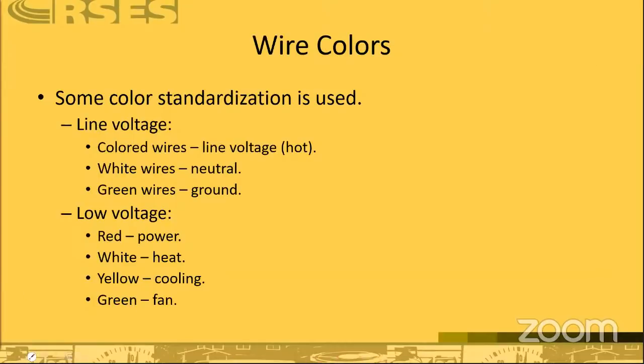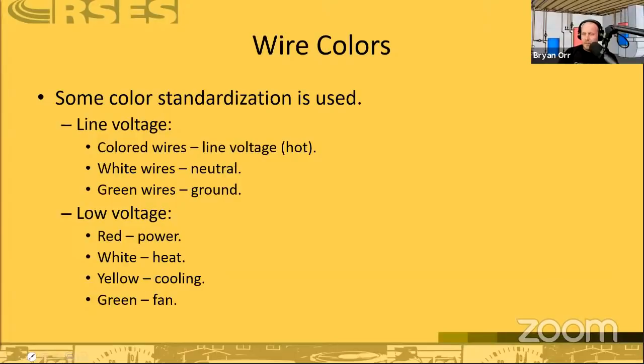Blue is common, and blue being common is one of the least set in stone, because you'll see black being used as common in some cases too. None of this really matters, you can use any color for any purpose, but as a standard we want to use the standardized colors. As another aside, if you're ever splicing wires in an 8-conductor thermostat cable, splice all 8 wires regardless of if you're only using 4 or 5. Splice all of them always, because you don't want somebody else to come along, try to use one of the other conductors, and find it's broken because you forgot to splice it. Always splice all the conductors, whether they're being used or not.